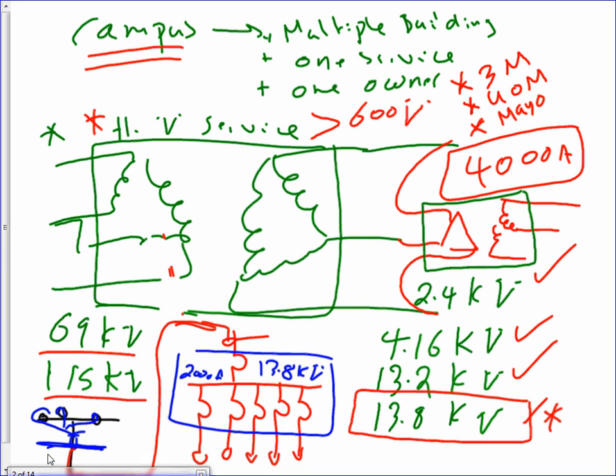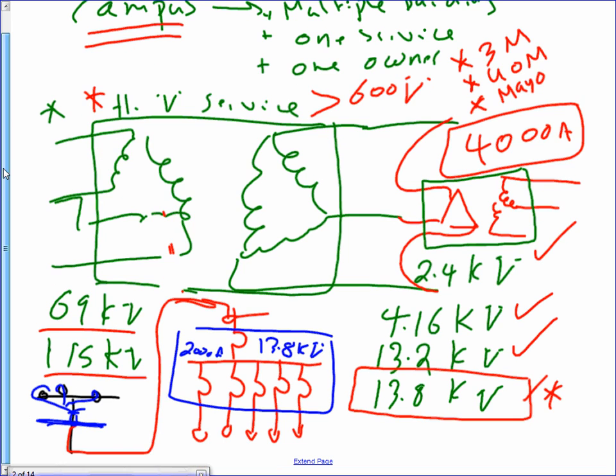Here's my 13.8 coming from the transmission line. I don't know if you can see it coming down slightly. So I have my transmission line bringing 115 or 69,000 volt in. You have a transformer here, so you transform it down. You have to have some type of transformer here. Transfer the voltage down into 13.8, 2000 amp, and you take 1, 2, 3, 4, 5 feeders. You take them and feed five big buildings like Mayo Clinic. Any comments, guys? Any questions about power distribution for over 600 volt?